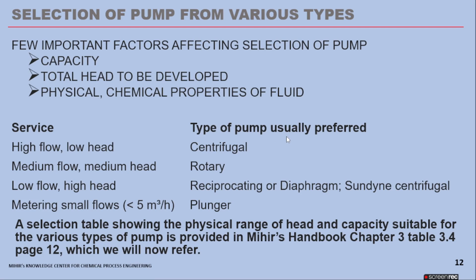A few important factors affecting selection of pump: capacity, total head to be developed, and the physical and chemical properties of the fluid. A summarized table for selection of pump from various types: for high flow, low head — go with centrifugal type; medium flow, medium head — rotary type; low flow, high head — reciprocating, diaphragm, or a sundyne centrifugal pump. Sundyne centrifugal pumps are a special type suitable for low flow, high head, operating at very high speeds of 12,000–15,000 RPM. For metering small flows less than 5 m³/hour, a plunger type is recommended. A selection table showing the physical range of head and capacity suitable for various pump types is provided in Mihir's Handbook, Chapter 3, Page 12.